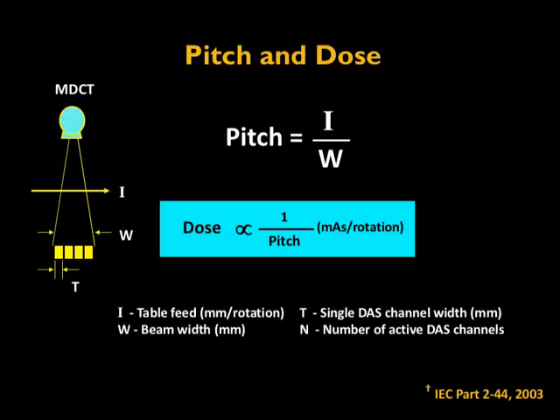We also perform many scans in helical mode. When you do helical mode, the concept of pitch arises. Pitch is defined as the ratio of table travel divided by the X-ray beam width. For example, if the table travels at 40 mm per gantry rotation and the beam width is also 40 mm, the pitch is 1 — meaning no anatomical gap is left. If the table travels faster with the same beam width, there can be an anatomical gap, translating to a pitch greater than 1. This is important because radiation dose is inversely proportional to the pitch value — keeping all other factors the same, if we change the pitch, the radiation dose changes accordingly.